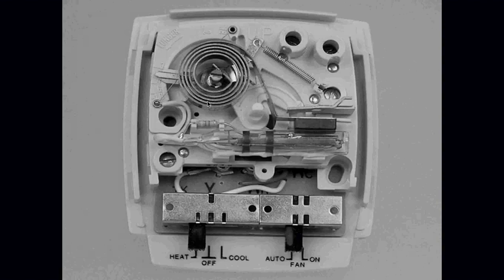Another type of subbase. This one has everything of the thermostat sort of mounted right on it, and then you have the wiring connections right under here. So you take these two screws out to get, or this one and this one, okay? And you have mercury bulb is right here. So again, this one matters if it's level. If it's not level, you're going to have incorrect heating and cooling. Okay, our switches are mounted on the subbase. Okay, and again, these are non-digital thermostats.